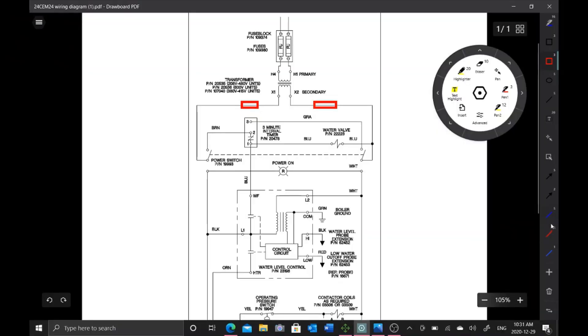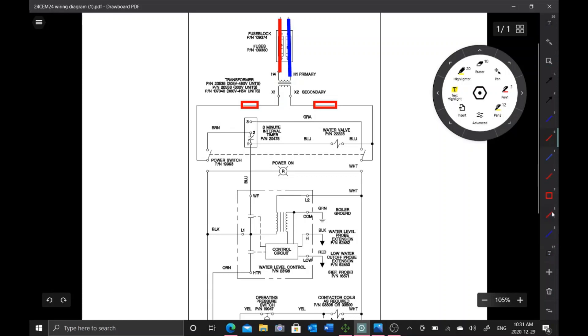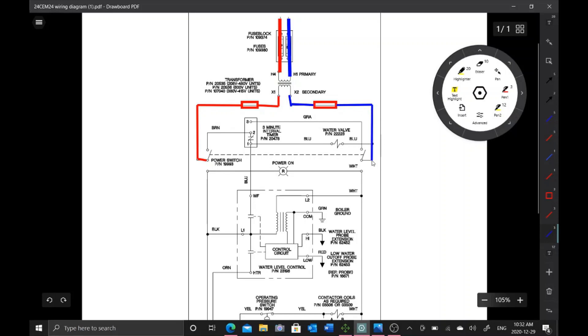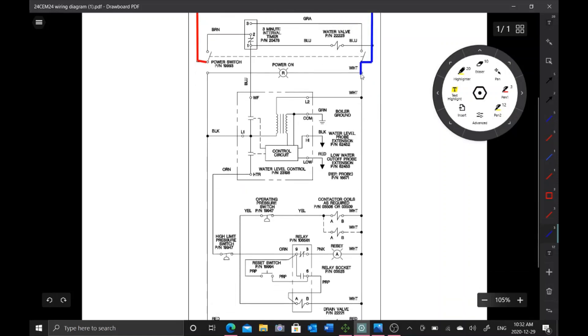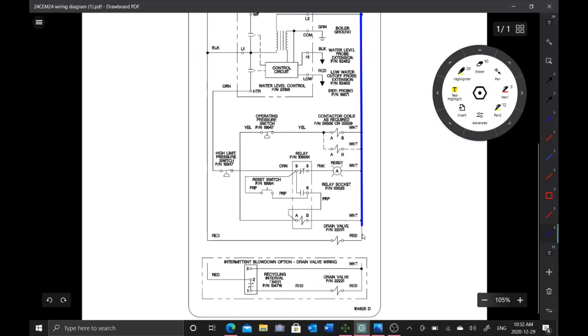We start through these fuses at 600 volts L1 L2, then we're coming out of our transformer at 120, in our case it's actually 130. We're coming out of our transformer here, we'll call L1 our red side. We're coming to our power switch, and then same thing's happening on the blue side. We're going to come through this temporary fuse that I installed, and we're going to come right down into this switch here. As soon as the switch is put in the on position, we're sending power down through here, so basically this whole side here is going to be hot as soon as we hit that on-off switch, and it's going to go right down to our drain valve.